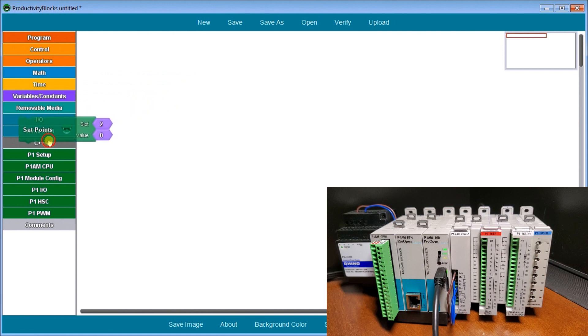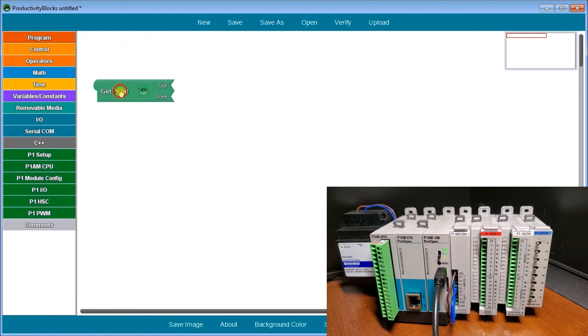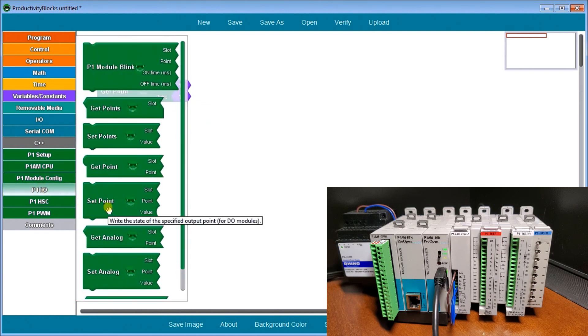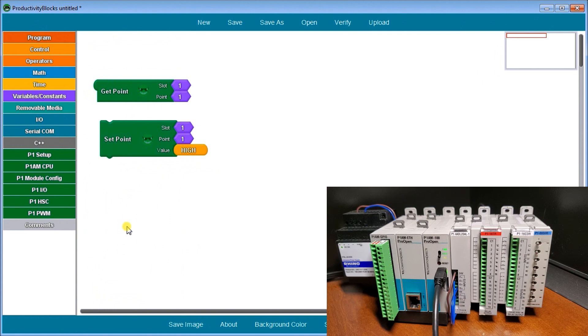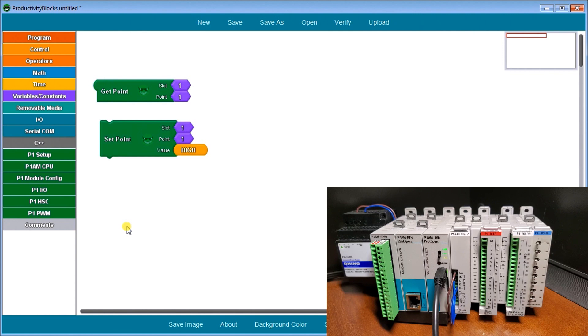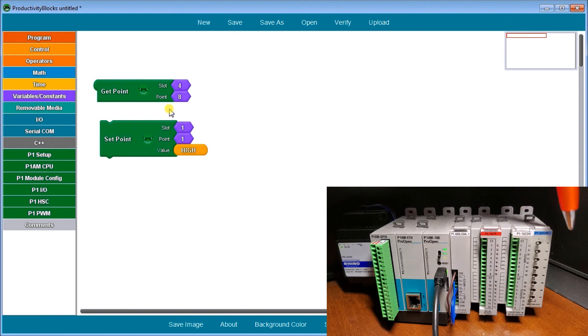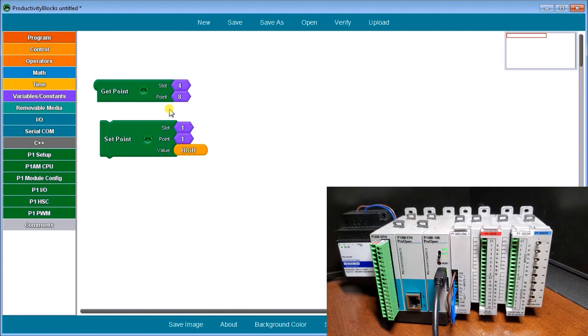Next we'll look at get point and set point. When dealing with get point and set point, we're dealing with a Boolean type expression, on or off, one or zero, high or low. Get point, we specify slot four, point number eight. We're looking at slot four, point number eight, which is the last switch of my card. It will return true or false, high or low.